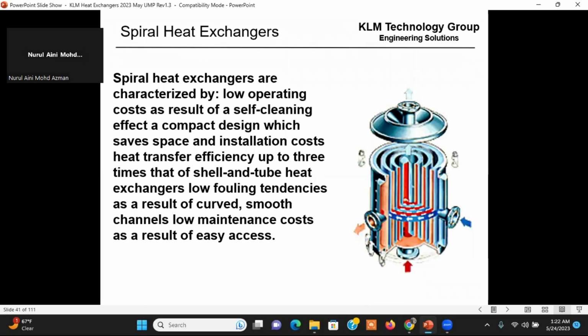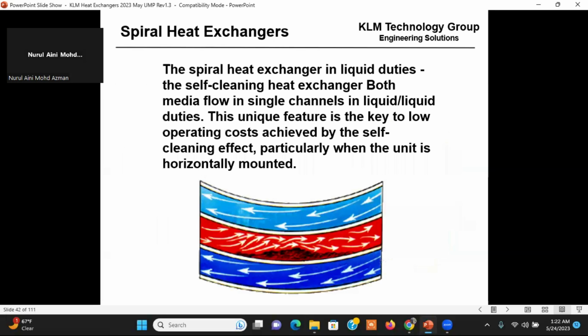Spiral heat exchangers look like this. The flow goes in a circle, so flow goes in one side counter current and out the other side. The solids can accumulate along the bottom and move out, so they're a self-cleaning, compact design. They're used a lot in utilities, and where you have high solids. What happens is the solids fall to the bottom and the flow generally moves them out of the heat exchanger. It has a self-cleaning effect, particularly when the unit is horizontally mounted.